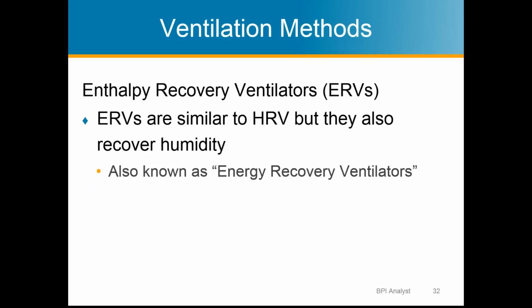And since we're talking about HRVs, I'll also mention there's an ERV, which is called an enthalpy recovery ventilator, or a lot of times an energy recovery ventilator, but it's actually recovering enthalpy, which means that it recovers the heat energy, but it also recovers humidity. This would be more useful in a situation not usually found in California, but let's say Florida, where it's incredibly humid a lot of the time. It could take some of the humidity out of the air before you're supplying it into the house, because a lot of energy from your cooling system is used to dehumidify the house. So if we can get the humidity out of the air before it enters the house, we don't have to spend more cooling energy just to lower the humidity.